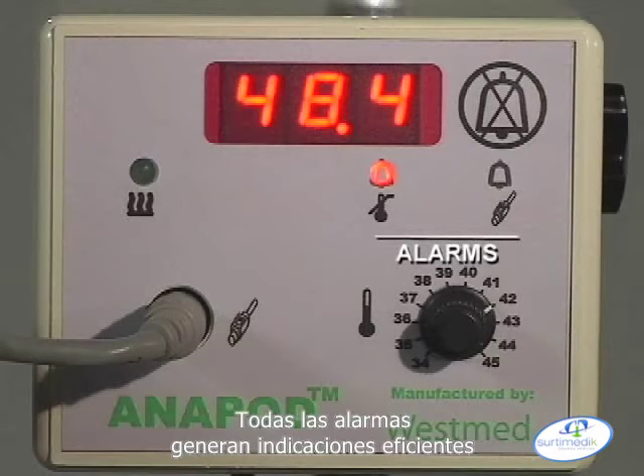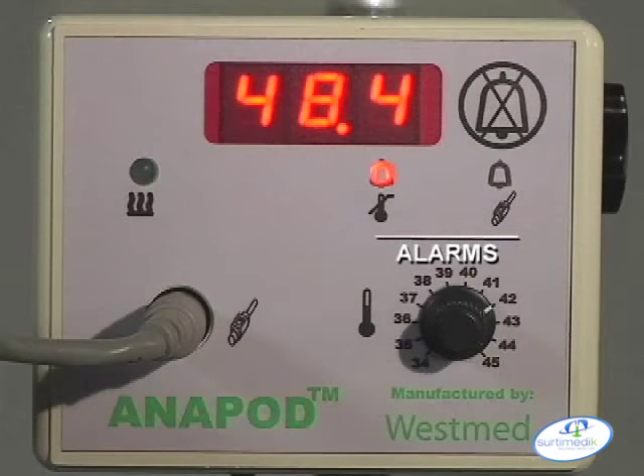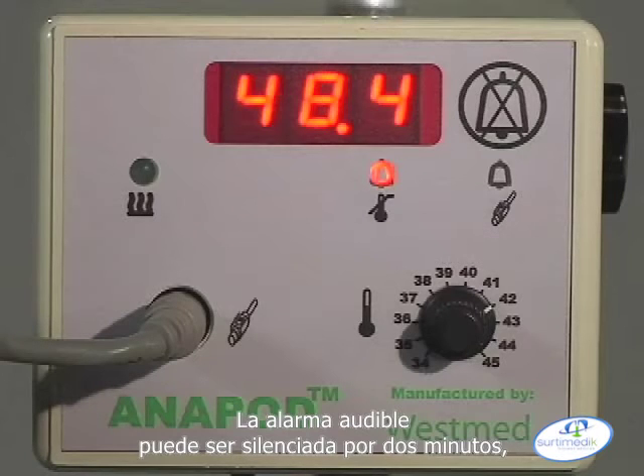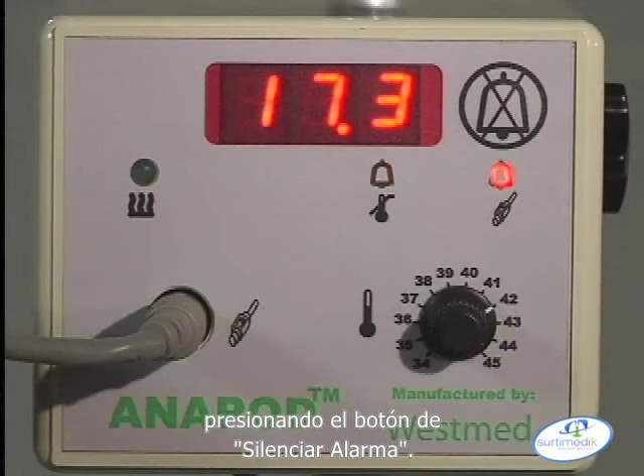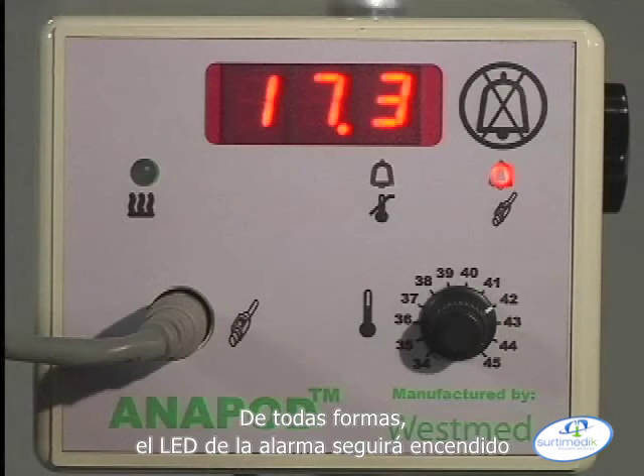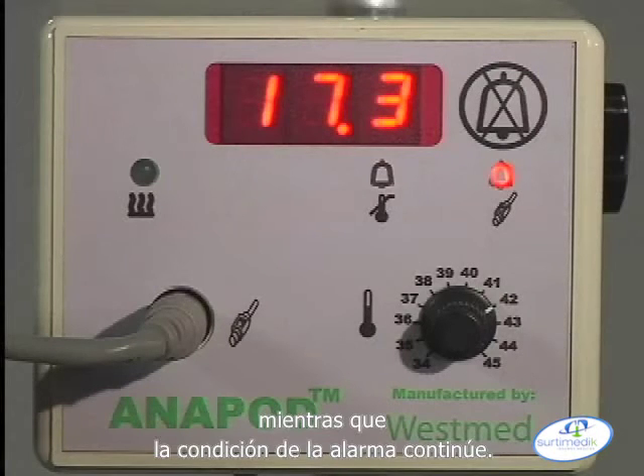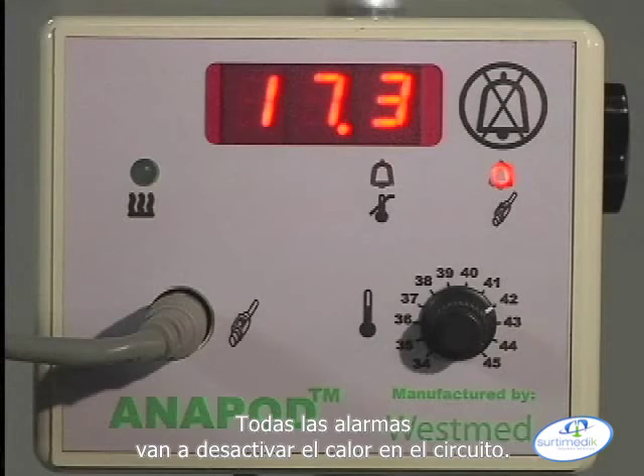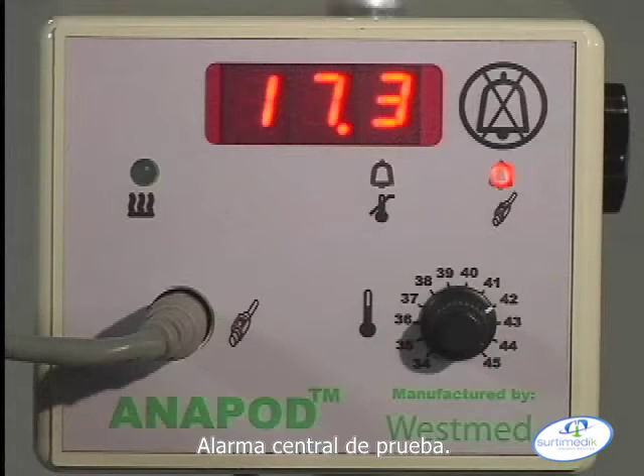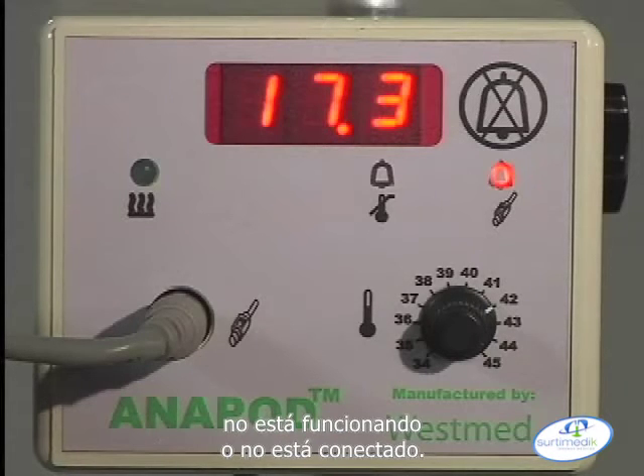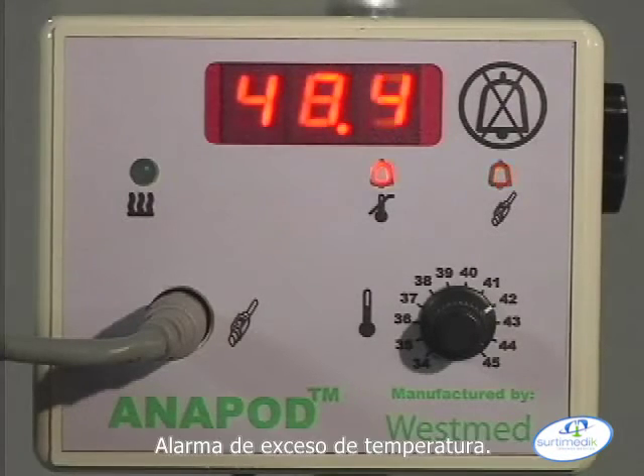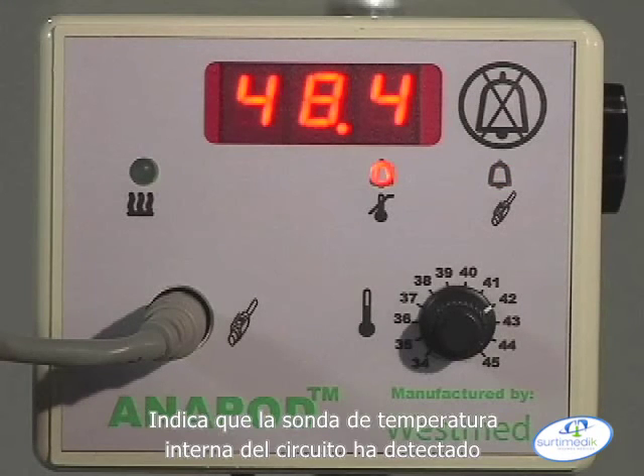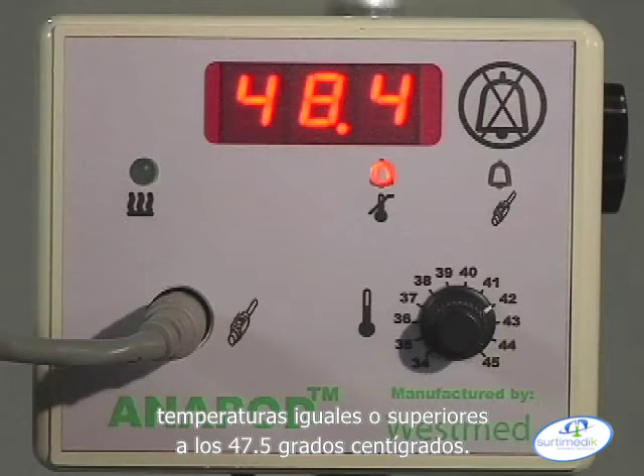Alarms. All alarms generate both a visual indication and an audible alarm. The audible alarm can be silenced for 2 minutes by pressing the alarm silence button. However, the alarm LED will remain illuminated as long as the alarm condition exists. All alarms will disable the heater in the wick circuit. Probe sensor alarm indicates the heated wick circuit has malfunctioned or is not connected. Over temperature alarm indicates the wick circuit internal temperature probe has detected temperatures at or above 47.5 degrees centigrade.